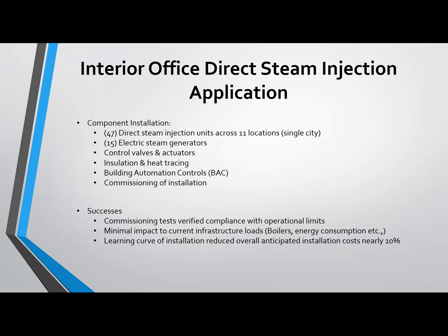We needed to put in 15 electric steam generators. A couple areas were not able to get the steam capacity we originally thought, and a couple facilities did not have steam generation available at all. So we needed to bring in a steam generator to make the steam, a structure-mounted unit not far from the unit itself, that pulls off domestic water, makes the steam, shoots it to the dispersion tubes, and out it goes through the duct.